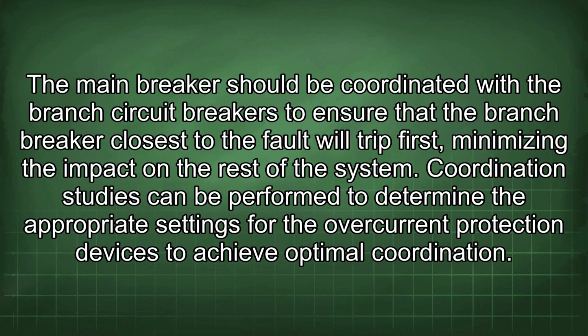Furthermore, it's important to consider the coordination of overcurrent protection devices within the panel board. The main breaker should be coordinated with the branch circuit breakers to ensure that the branch breaker closest to the fault will trip first, minimizing the impact on the rest of the system. Coordination studies can be performed to determine the appropriate settings for the overcurrent protection devices to achieve optimal coordination.